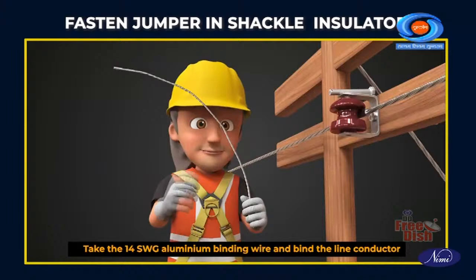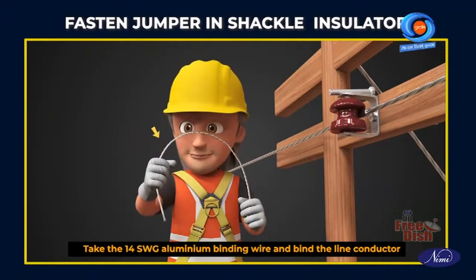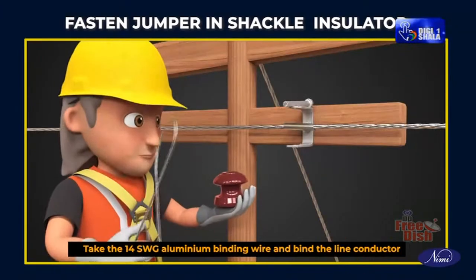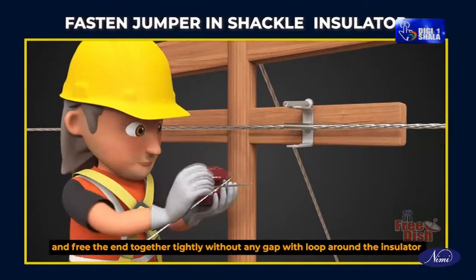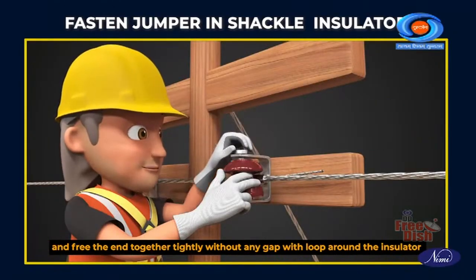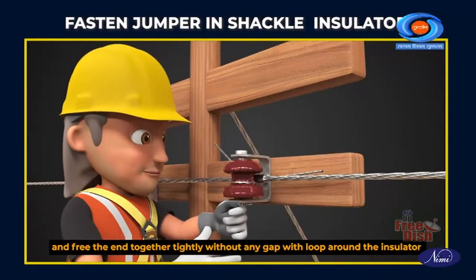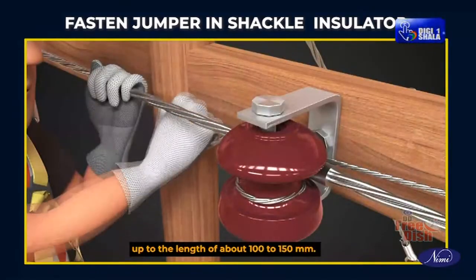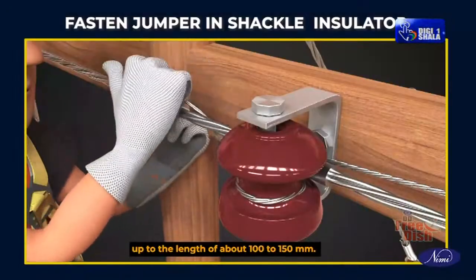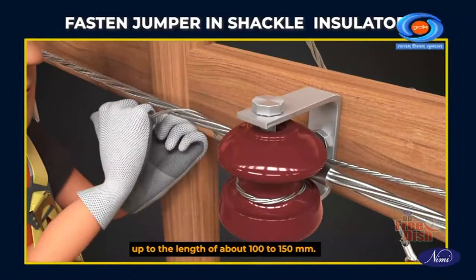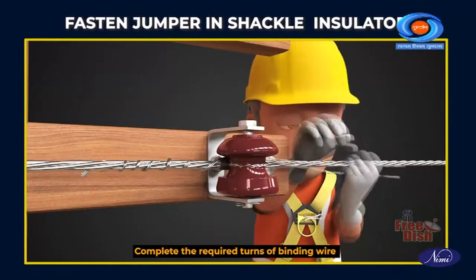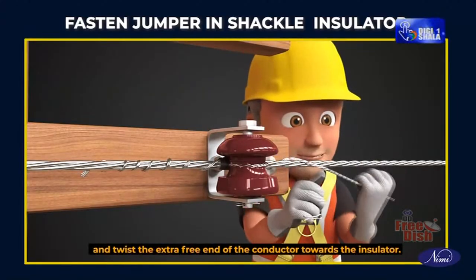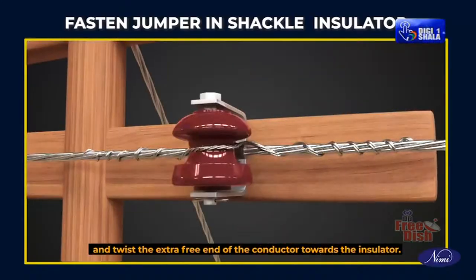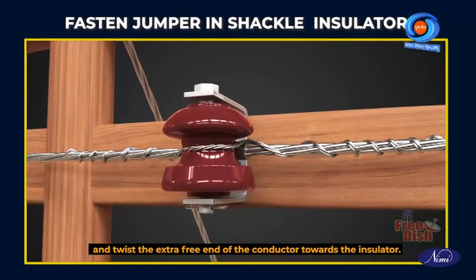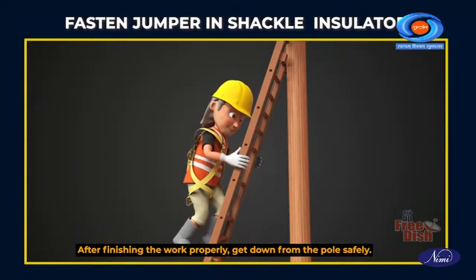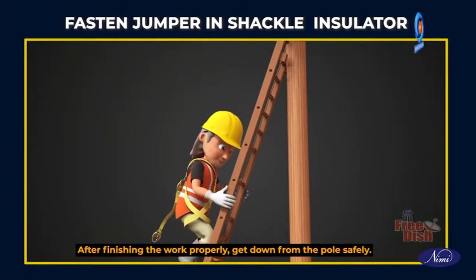Take the 14 SWG aluminium binding wire and bind the line conductor and free the end together tightly without any gap with loop around the insulator up to the length of about 100 to 150 mm as shown. Complete the required turns of binding wire and twist the extra free end of the conductor towards the insulator. After finishing the work properly, get down from the pole safely.